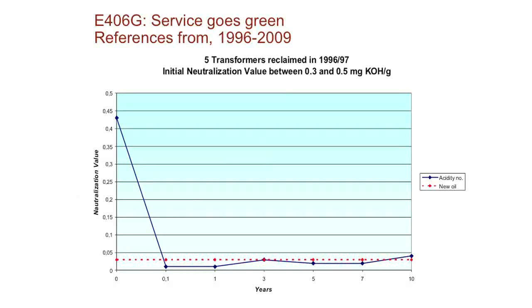Any questions regarding the process for oil reclamation? Let's move into a second option, and that's an ABB Biotemp product. There are two options. We can do a retrofill in the field on the existing equipment, or retrofill can be considered during a remanufacturing of your transformer when you bring it into the factory. Both are options.